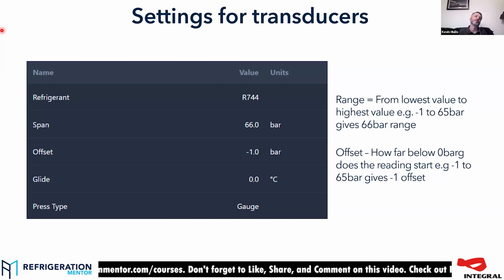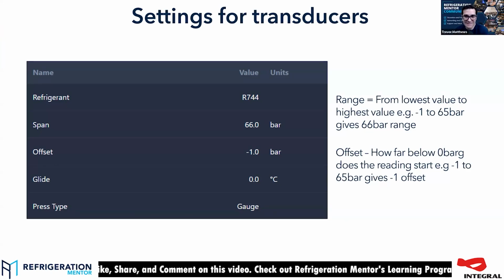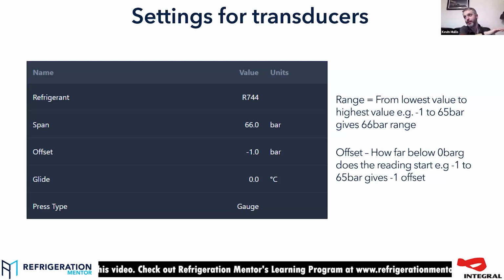I think what happens sometimes as well is people tweak the span or the range, or whatever it's called on the controller, to try and correct errors in the reading. That is not going to be a happy place for you. If you're 0.1, 0.2 out, adjust it with the offset. Don't adjust it with the range because the span will give you error right through the operating range. Just adjust it with the offset because that is a fixed amount that it moves the reading by. If you adjust the range, you're going to be like, why is it out now? Why is it out more? Why is it out less? It's going to be all over the shop.